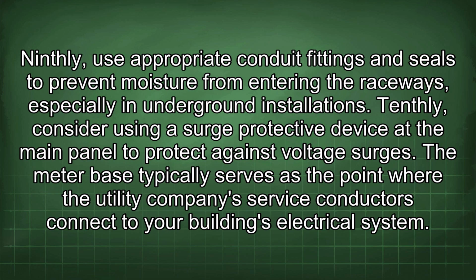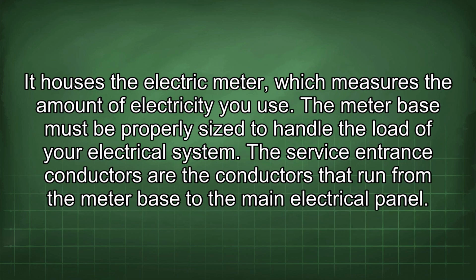The meter base typically serves as the point where the utility company's service conductors connect to your building's electrical system. It houses the electric meter, which measures the amount of electricity you use. The meter base must be properly sized to handle the load of your electrical system.